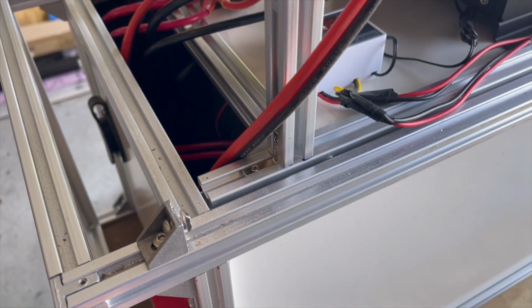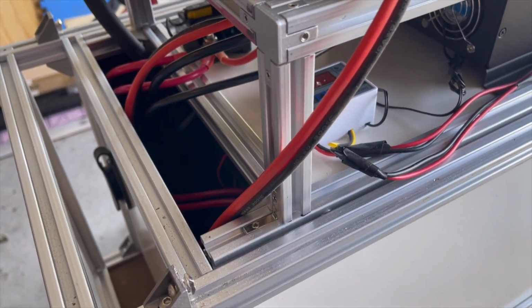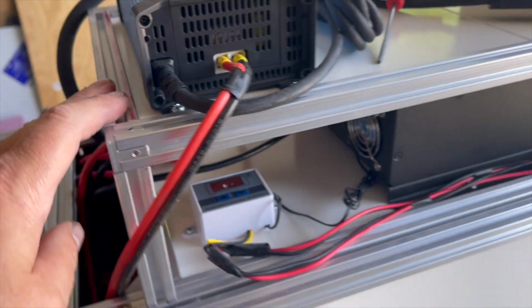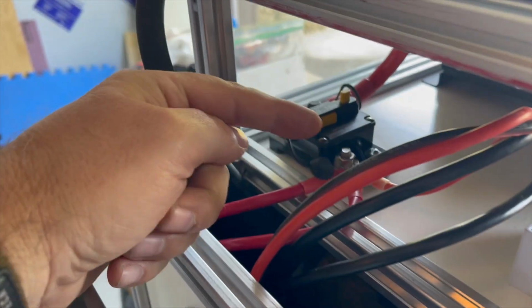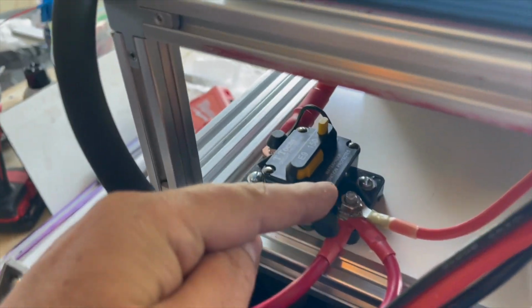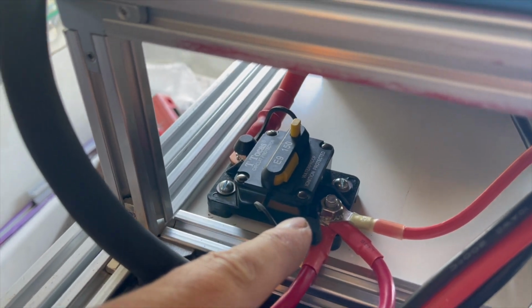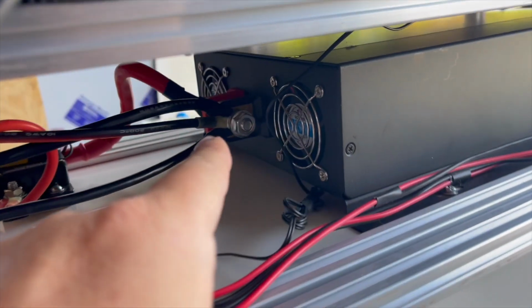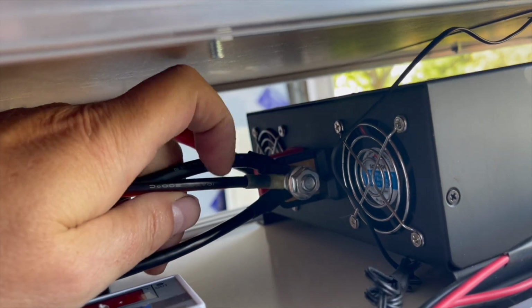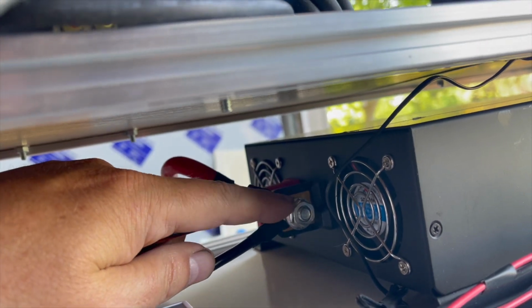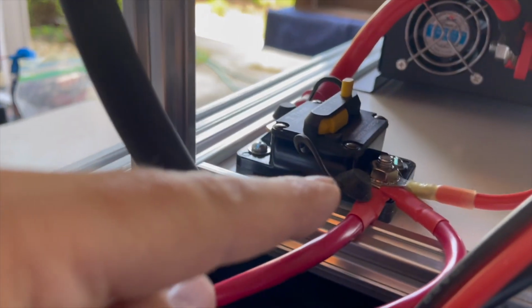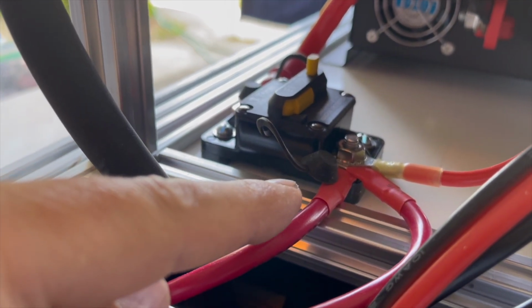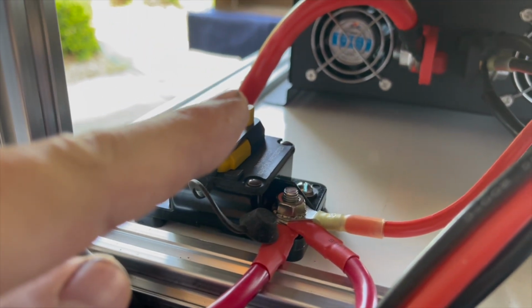just to this tray by itself. I've got it disconnected, but the battery in the base box is still connected up, and the battery leads come to this tray, and there's really kind of two poles here. I'm using this bolt on this breaker as one pole, and then I'm using the negative side of the inverter as the other pole, so that's where the 12 volt leads come in. So that's the negative side, and then this is the positive side, and then the positive side runs through the breaker to the inverter over there.